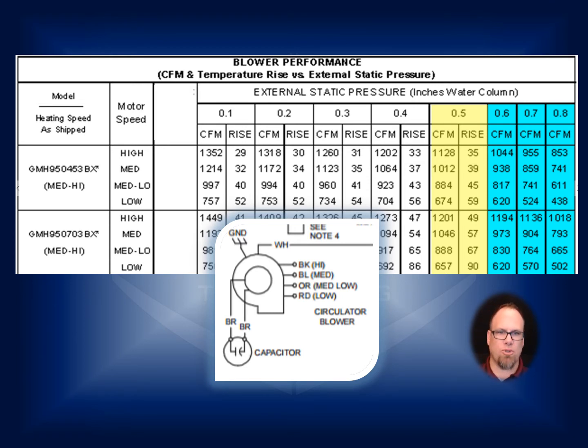You add the raw numbers together. Now, for those of you mathematicians, that might be a bit of a tough stretch, right? You stick it before the blower, it's sucking, so it's a negative pressure. You stick it in after the blower, it's blowing, so it's a positive pressure. We don't care about the negative and positive. You take the negative and positive, you crinkle it all up, and throw it in the floor because we're adding raw numbers. So in this instance, if you measured your static pressure and it was negative 0.4 before the blower and positive 0.4 after the blower, those don't equal 0 in this particular example.